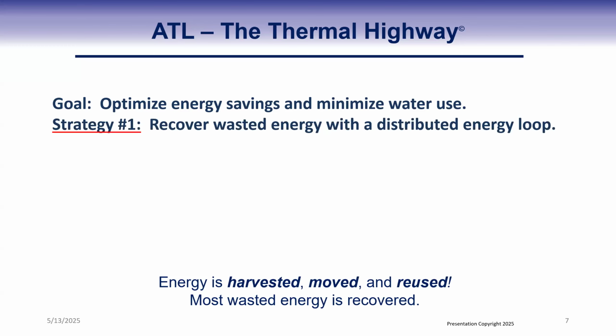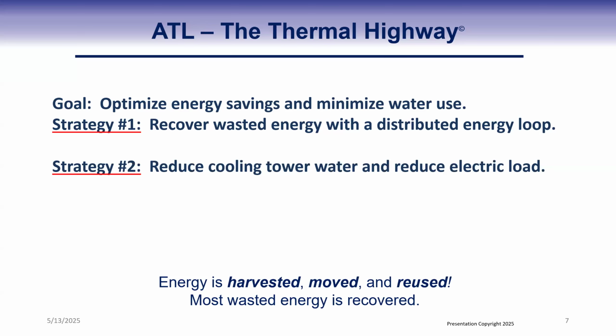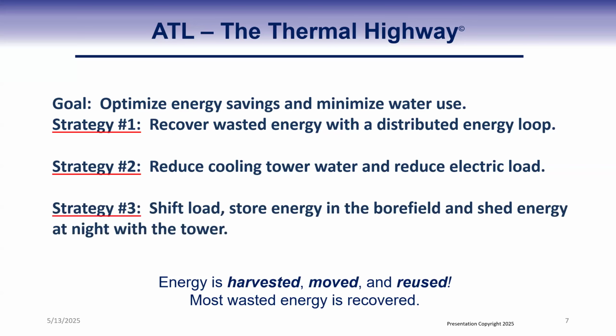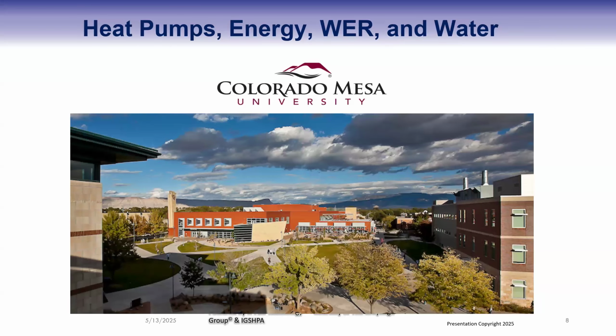We want to recover the wasted energy with the distributed energy loop. We want to reduce the cooling tower water and reduce electric load. And then we want to shift load, store energy in the borefield, and shed energy at night with the towers so that we can take advantage of our lower wet bulb temperatures.